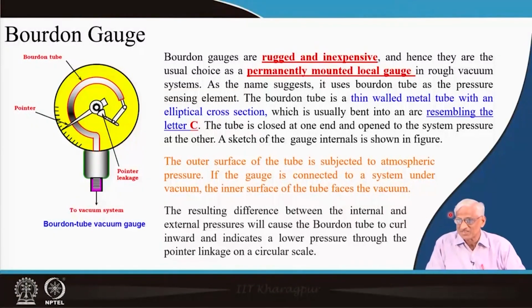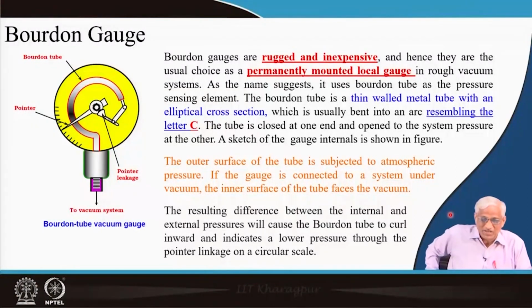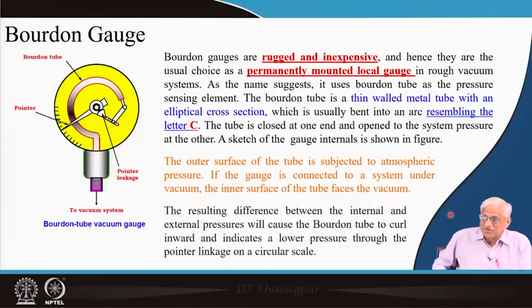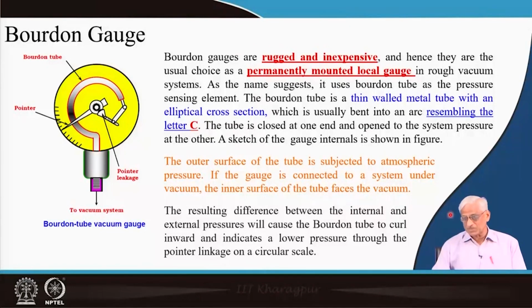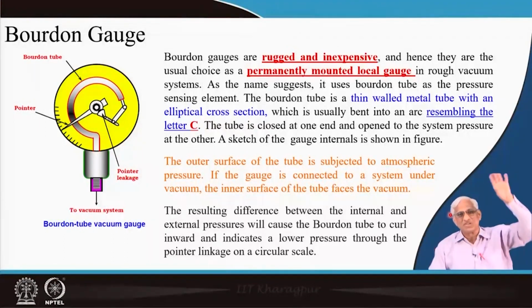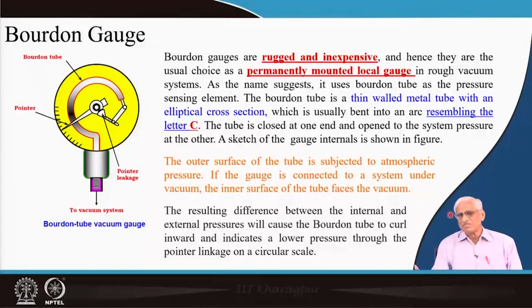That is a relative accuracy. So, you have to be careful in process applications. Why I am talking like this is, when these gauges are used in process application, because the whole subject is on vacuum technology and process application, you have to understand which gauge to rely under what situations. Unnecessarily, you should not use a very sophisticated gauge when pressure can be measured plus or minus 10%, 20%.